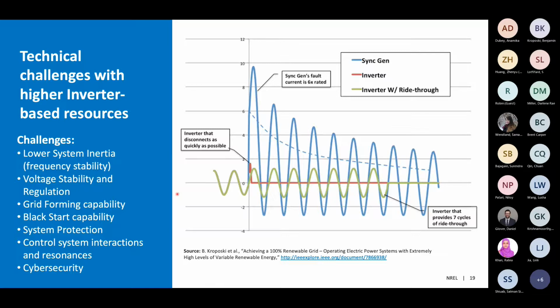So there are a variety of technical challenges that you have to deal with when you're thinking about integrating these inverter-based resources. At a high level, I've talked about system inertia, frequency stability, voltage stability, and regulation. I'm going to skip these two and come right back to them, but I'll talk about system protection real quick. System protection means we need to be able to recognize fault conditions in the grid and respond appropriately. A lot of times we have built past protection systems on the fact that synchronous generators are able to provide a lot of fault current when they're under a fault condition.